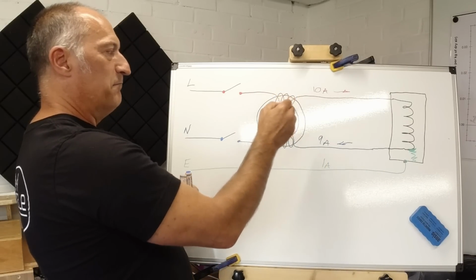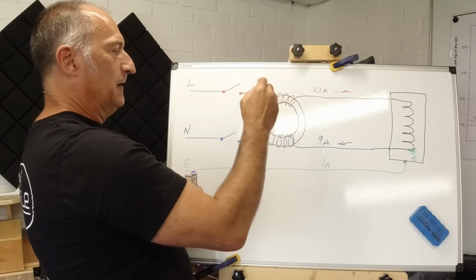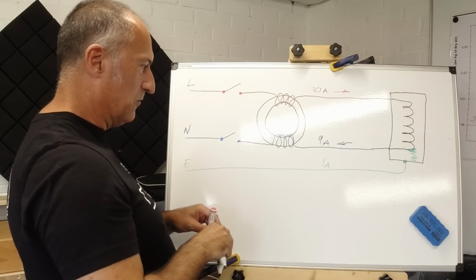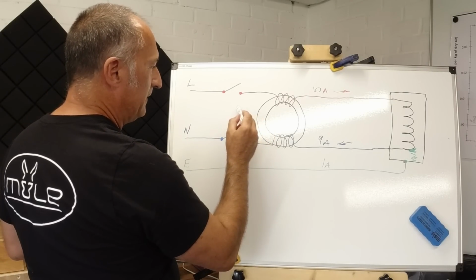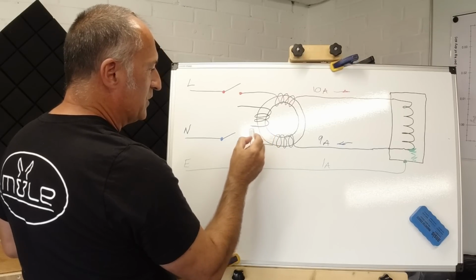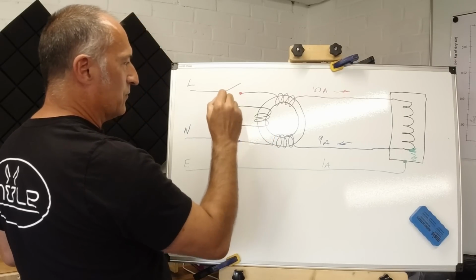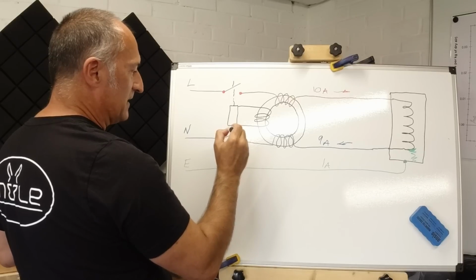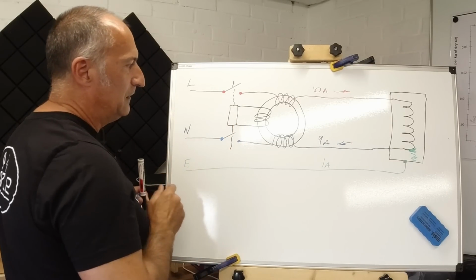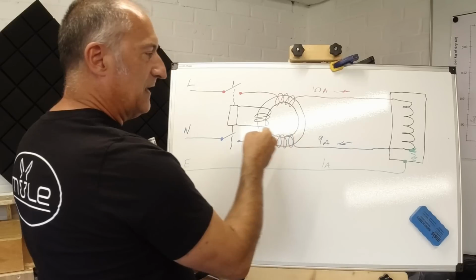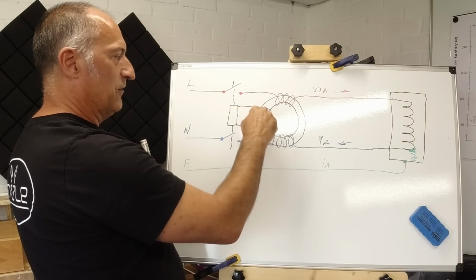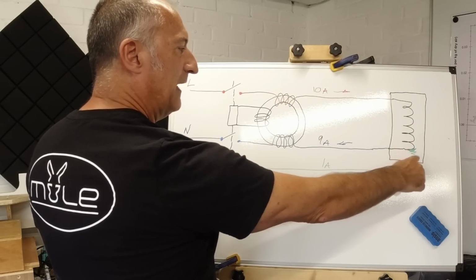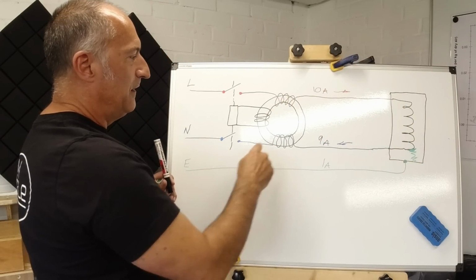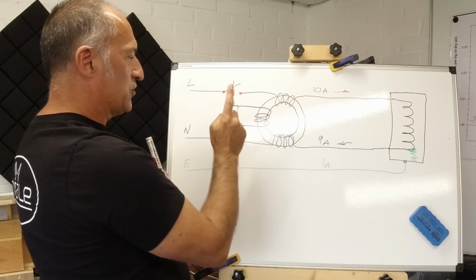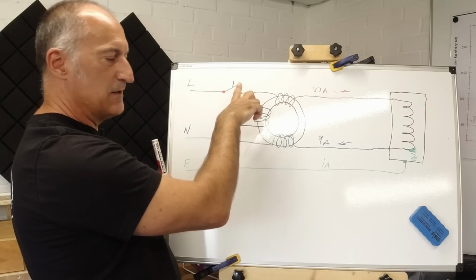So what happens is this magnetic field in here becomes stronger, and there's a small little coil in here. Wrapped around here is another coil which is monitoring that imbalance, connected to a little solenoid, and that solenoid is connected to these 2 switches. So all the time that circuit is in balance, nothing happens to this solenoid. But as soon as we get a fault and that current leaks back down the earth, then there's an imbalance in this coil which triggers this solenoid, which breaks these 2 switches.